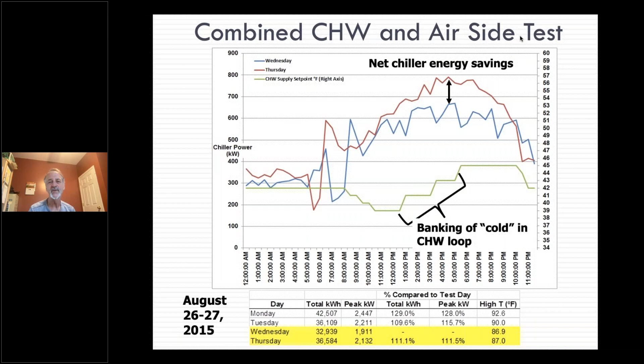Some lessons learned: set points could be altered, maybe even higher than what we did, but you have to think about this depending on the type of building. What's the optimal set point change? When do we start it, when do we stop, and how do we avoid the rebound effect?